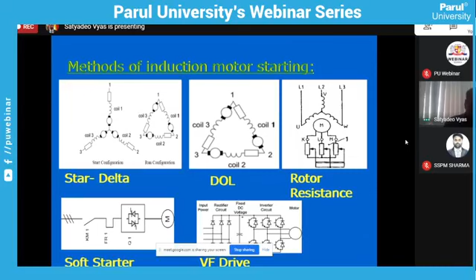So the VF drive is used for speed control of the motor as well as for soft starting and stopping of the motor. Whereas the soft starter is used for soft starting and soft stopping of the motor. We cannot control the speed of the motor by soft starter.